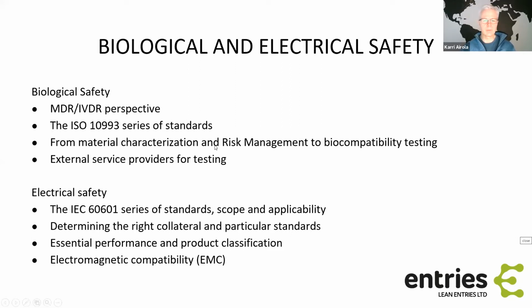And so then the approach is pretty much from a risk management perspective. Whenever we are developing and designing a new product, risk management is at the core. It's at the core in assessing the biological safety as well. The biological safety is part of the verification you need to do during the design, and it's intended that the biological safety assessment gives you some ideas about possible risks related to your product idea, or to the product which is under development.